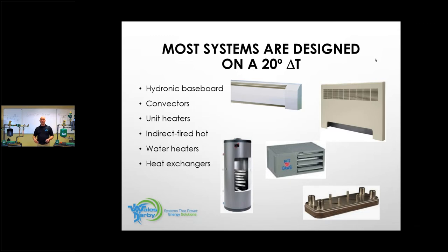Down here where I am in New Jersey, it's 14. Around Long Island, it's 14. So depending on where you are, there is a design outdoor temperature that you design for. All of these different heat emitters have a 20 degree delta T. So if you're unsure what the delta T of the job should be, unless it's radiant, you can probably assume 20 degree delta T, and that will get you in the ballpark for sure.